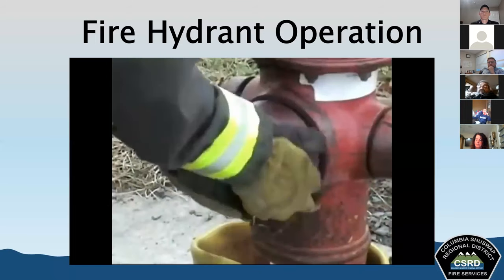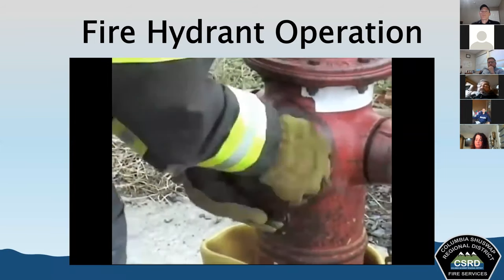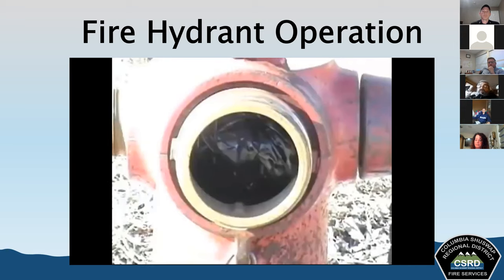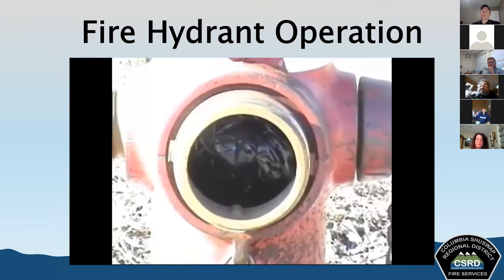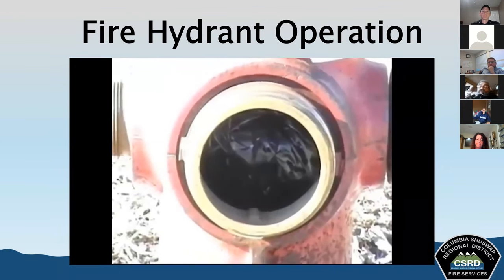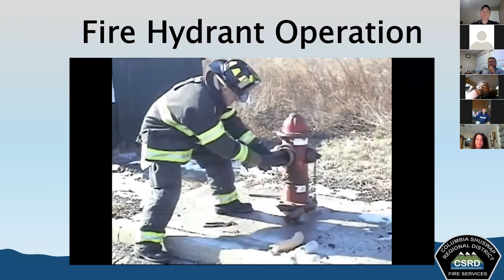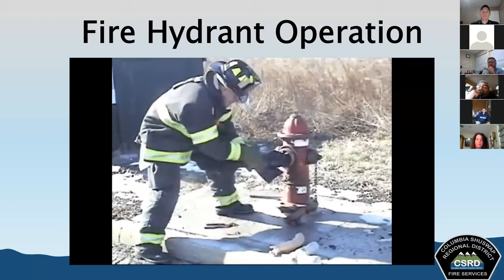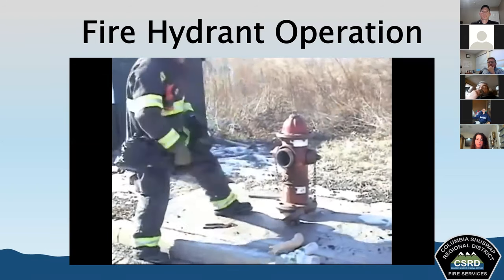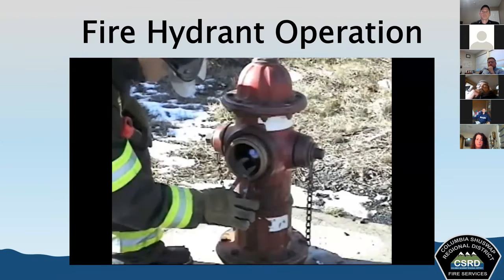Always remove the large steamer cap first, as this provides the maximum access to view the hydrant's interior. Once the cap is removed, look into the opening. The barrel should be dry and free of debris. If it's not, inform the officer the hydrant may be out of service. If there is garbage in the barrel, it must be removed.